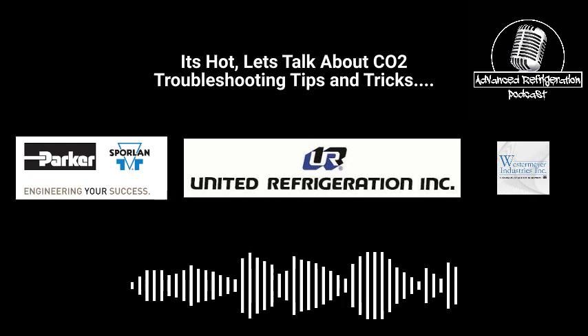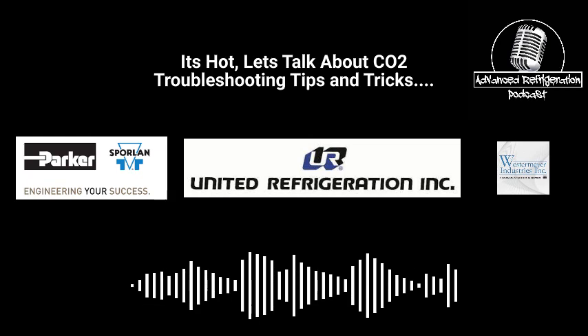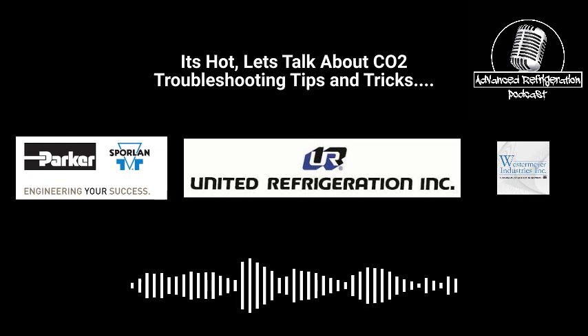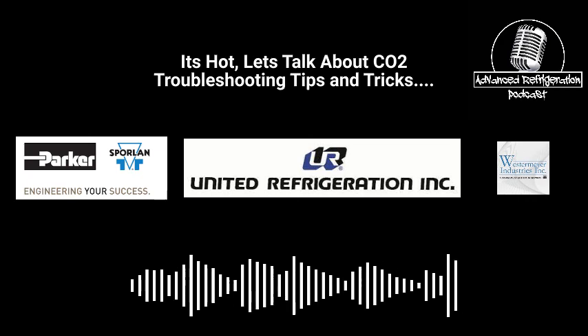Gotcha. So anytime we're having head pressure issues, a lot of times if it's not a dirty condenser, it's more than likely receiver pressure issues. Flash gas bypass valve failed, something like that. The high pressure valve sticking open. But generally, if we have something like that, then the obvious thing would be to try to calm down the rack by pumping everything down at that point, right?